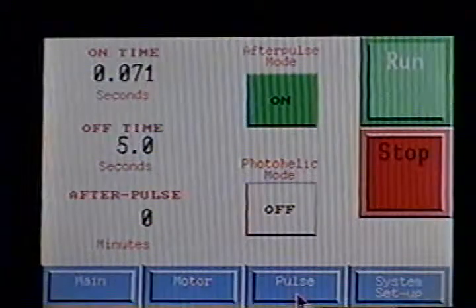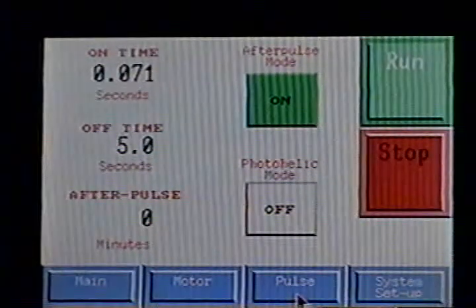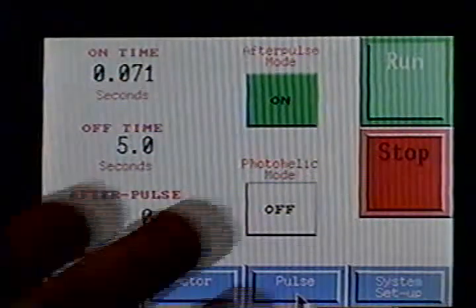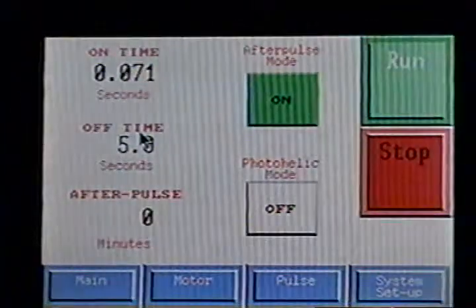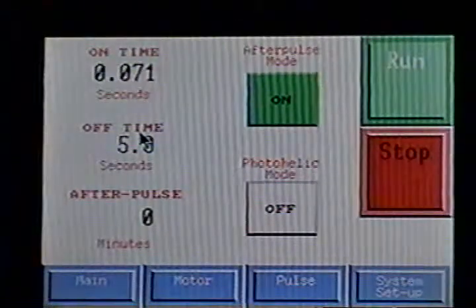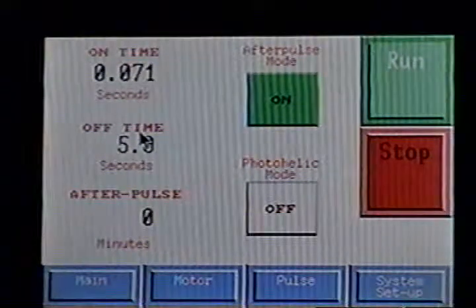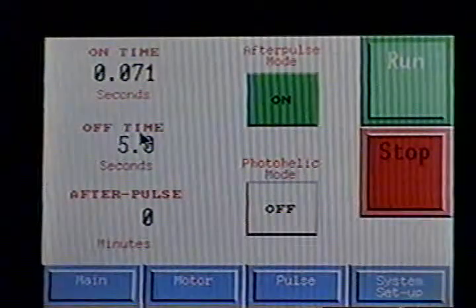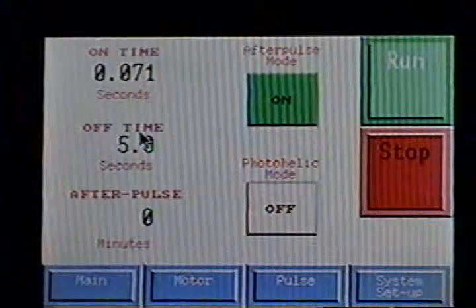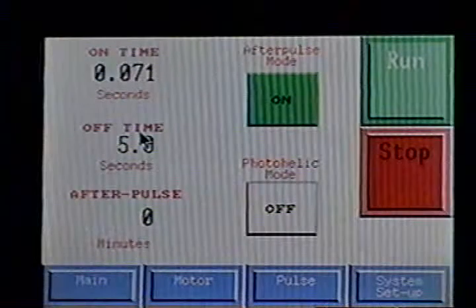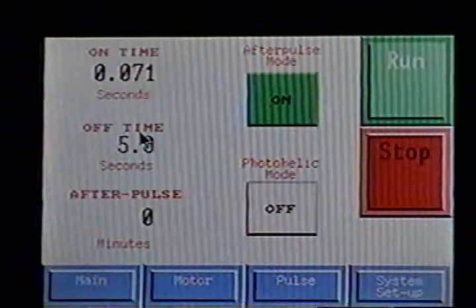You've got the amps, display information here, pulse settings. Currently my pulsing is set at 0.071 second on time, 5 second off time, and I have my after pulse set at 0. This is a display only screen, and the reason it is, I know that there are times where you don't want people to mess with what you've set up. There are controls in place so that they can see this information but may not be able to adjust it. So that you don't have the guys running the unit coming over and messing with the controls. There's a way to lock them out with codes that you can go in and just say, I'm this level of code, I can make these changes. So we're displaying information you can't necessarily change from here.